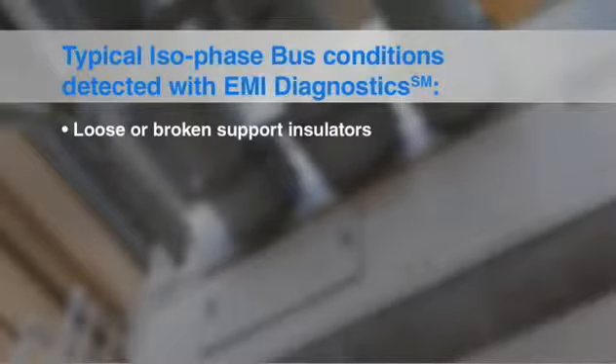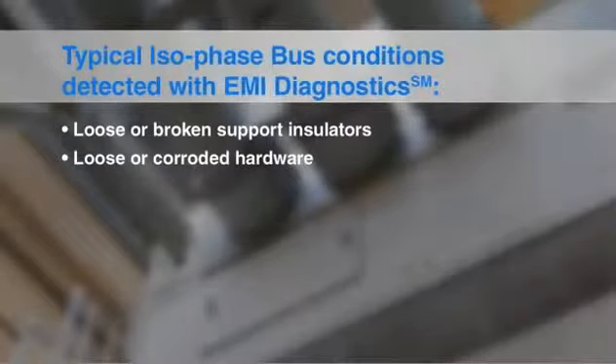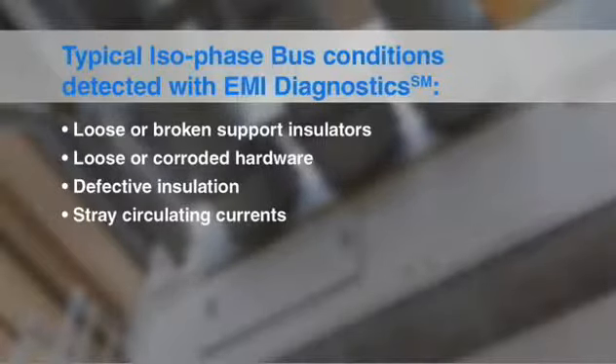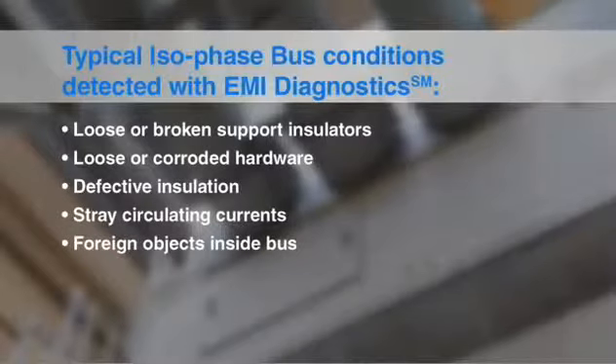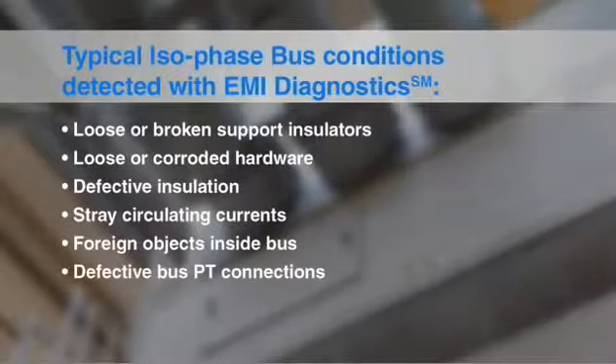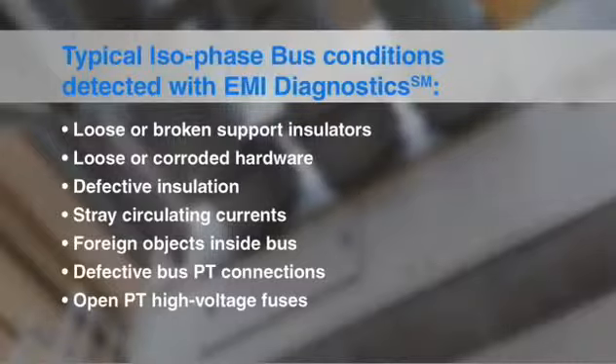Typical isophase bus conditions detected with EMI Diagnostics: loose or broken support insulators, loose or corroded hardware, defective insulation, stray circulating currents, foreign objects inside bus, defective bus PT connections, open PT high voltage fuses.